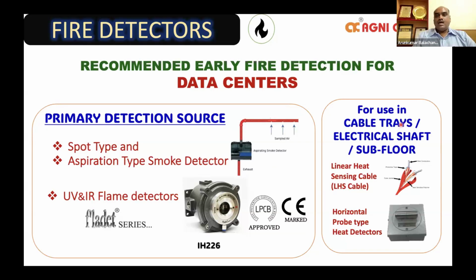Similarly, in data centers and many applications, there are a lot of cable trays, electrical shafts, and subfloors where linear heat sensing cables and horizontal type probe type heat detectors are recommended. Again, a question will come where normally a spot type smoke detector is mostly sufficient. Well, in Indian applications, especially in India, most of the subfloor after a period of time becomes very, very dusty, and using a smoke detector is going to give a false alarm. After a period of time, those detectors would normally be isolated and kept out of the detection zone. In order to avoid that, we have been recommending an LHS cable or a horizontal type probe detector in these areas, that is the cable trays, shafts, as well as the subfloor.